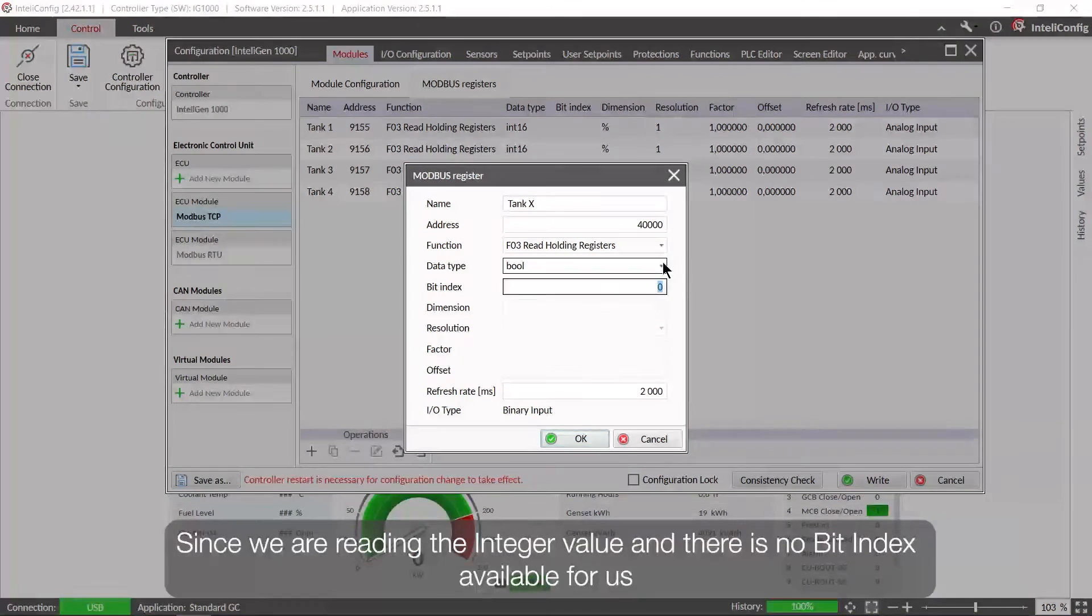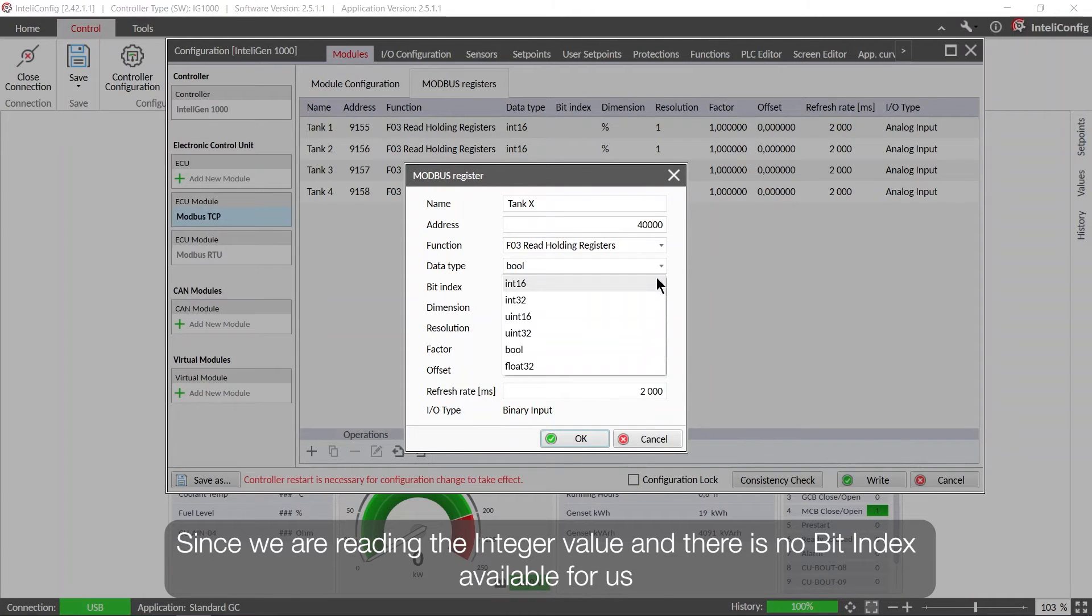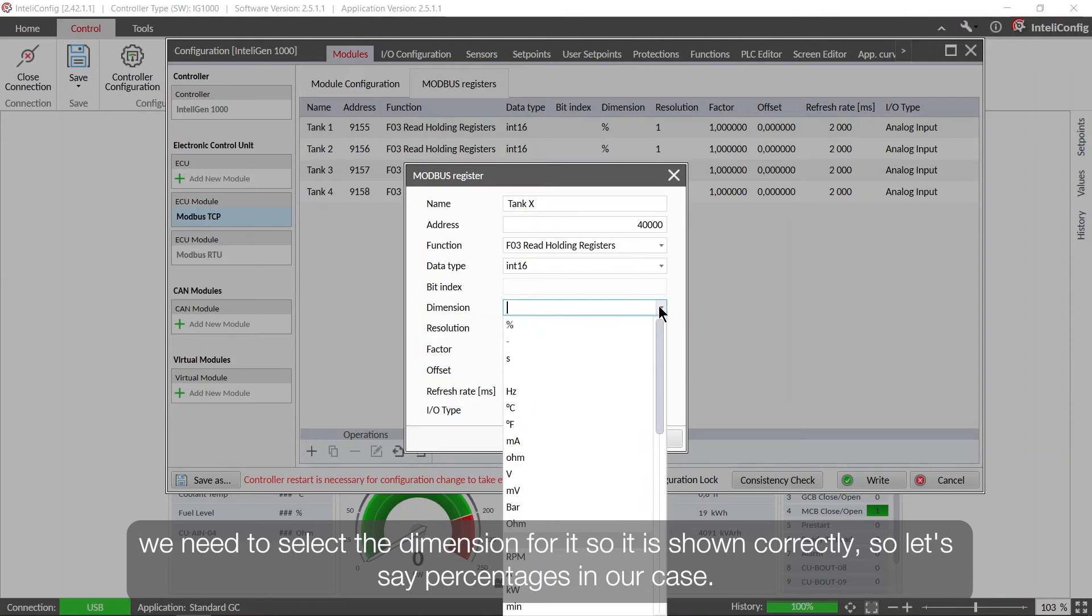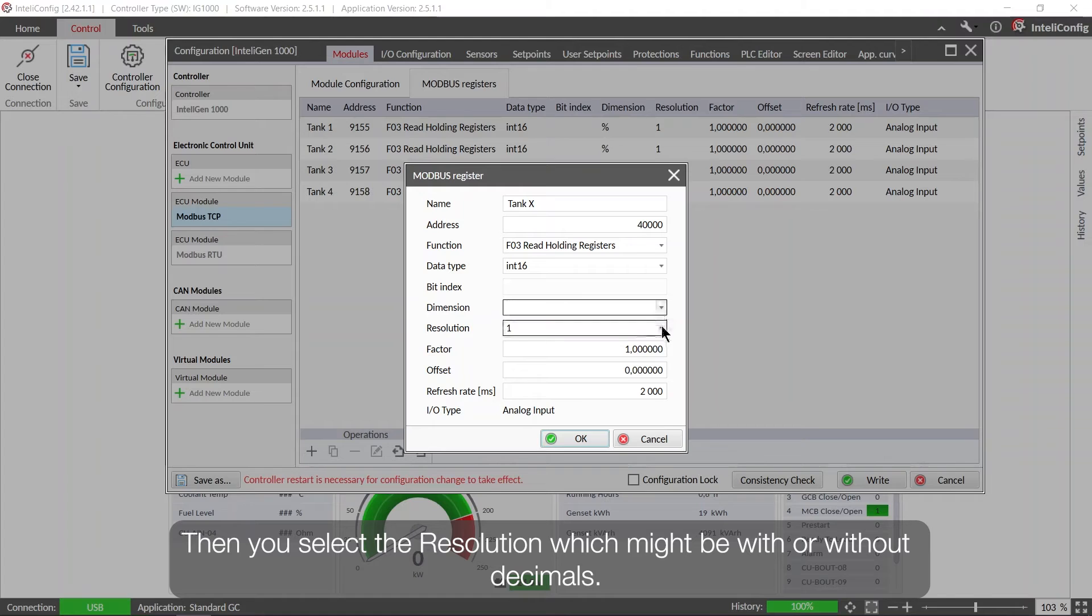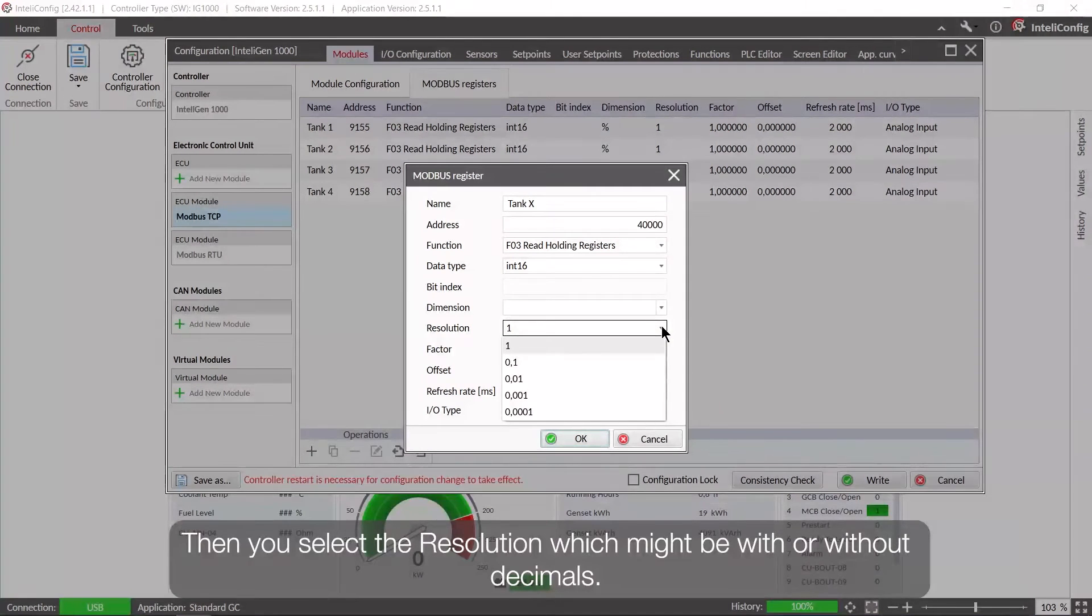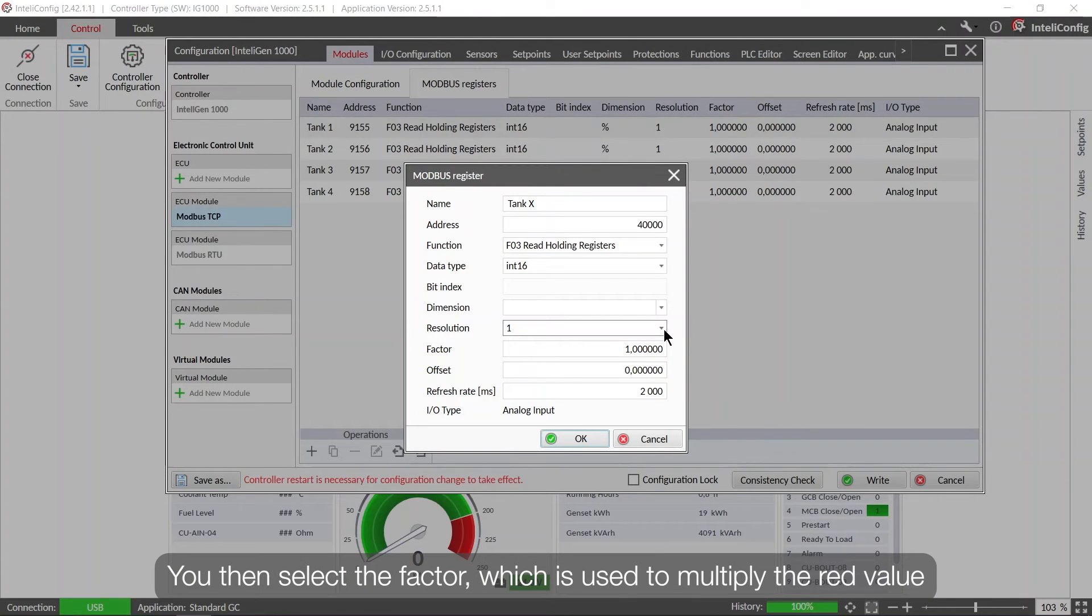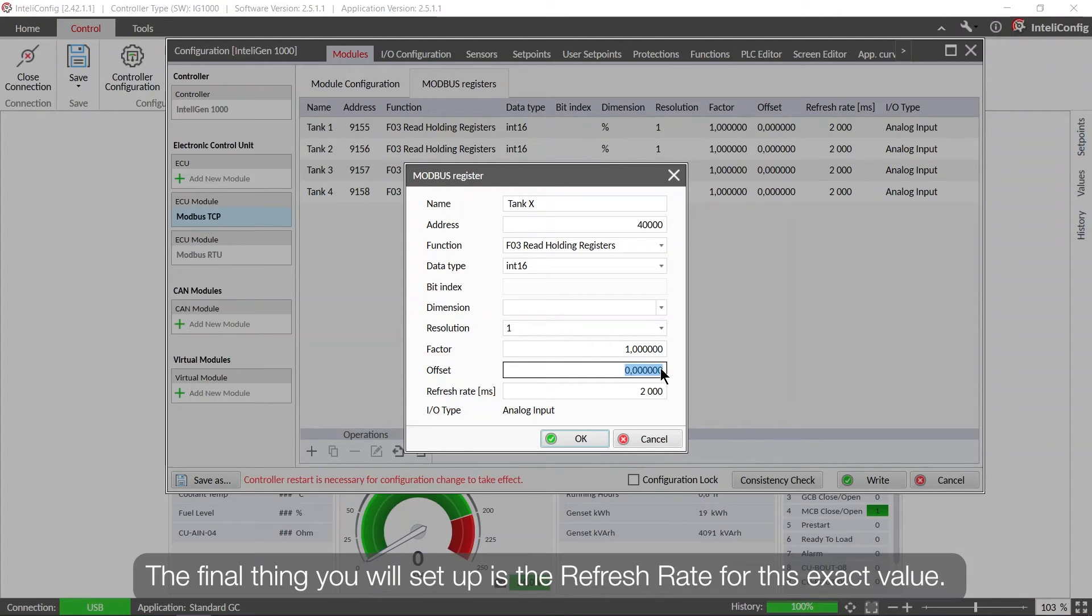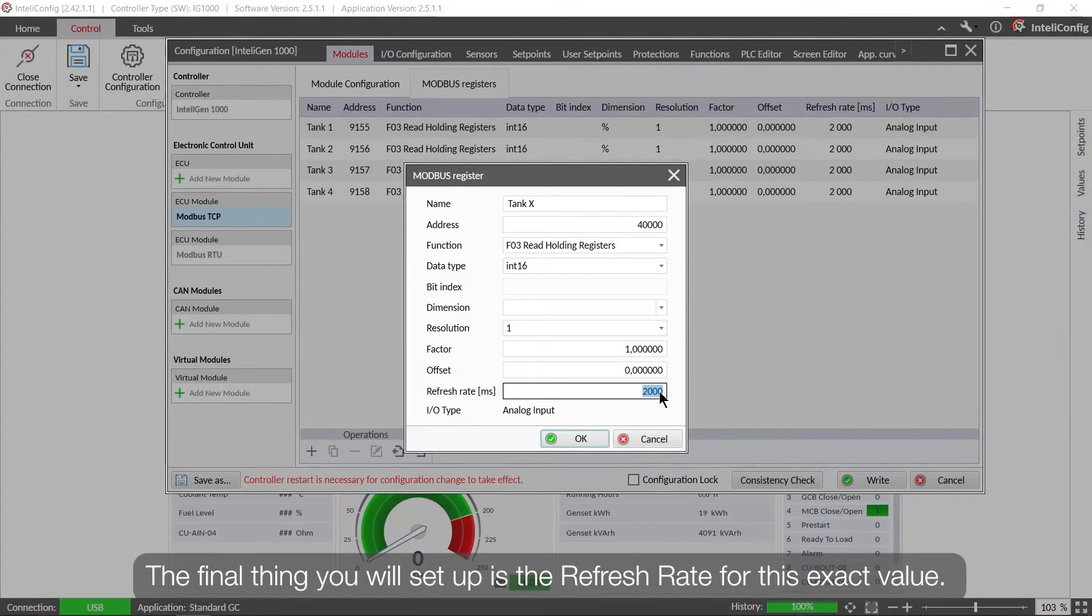Since we are reading the integer value, there is no bit index available for us, so we need to select the dimension for it so it is shown correctly. So let's say percentages in our case. Then you select the resolution which might be without the decimals or with. You then select the factor. Factor is used to multiply the read value and of course its offset. The final thing, you will set up the refresh rate for this exact value.